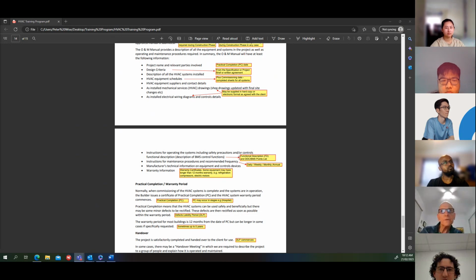If there is a DDC and BMS, it's good to include the points list as well, so that anyone can look at the inputs and outputs and how things are supposed to function. The DDC points list and functional description can be read together. The functional description is an English language description of how things operate, and the points list gives you the inputs and outputs, so those two things should match. That's one of the procedures when checking the control systems — making sure they do match. That's important.